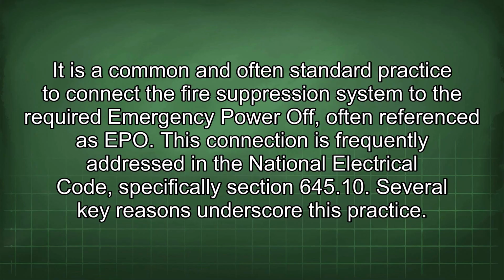It is a common and often standard practice to connect the fire suppression system to the required emergency power off, often referenced as EPO. This connection is frequently addressed in the National Electrical Code, specifically Section 645.10. Several key reasons underscore this practice.